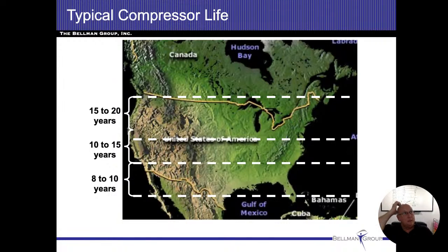All right. Lifespans in our area, and if somebody disagrees with me, you're good with that. But we usually tell our clients they'll get roughly about 20 years out of an air conditioning system. Sometimes we'll say 15 to 20 years. So it depends on how much it's using it, how many heat loss days or heat gain days there are, is how long the air conditioner is going to actually be running. So down in Florida, Texas, Arizona, where the temperatures are a lot hotter and everybody's using these things more, obviously they're going to have a shorter lifespan.